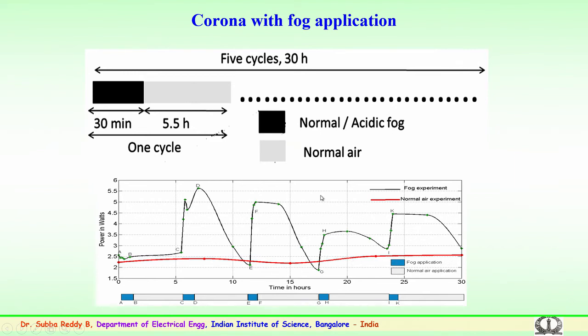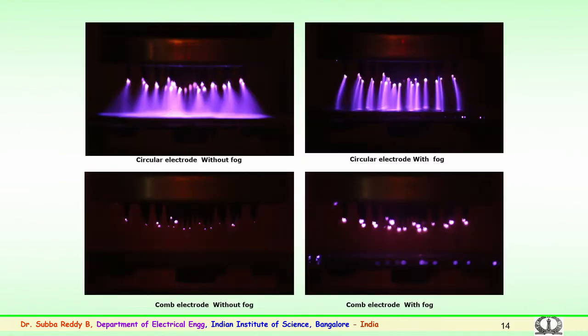but in case of fog or acidic fog, you can see an increase in the magnitude of the power over a period of time. This graph is shown for the normal fog conditions. So, a comparison is made between the dry condition and the fog, where the magnitude increases. The power consumed by the sample, the power flow into the sample, is much more in case of fog or acidic fog. This would create surface changes over a period of time in case there is a mist with corona discharges on the surface for a long period of time.